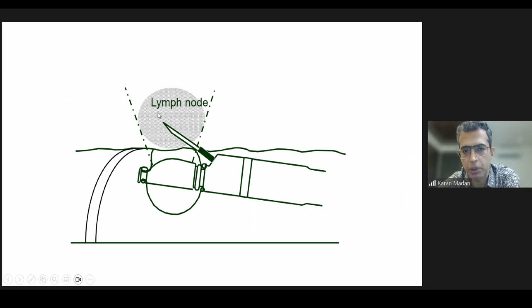Now coming to how it actually looks. This is the real image of two EBUS systems which we have at our facility. These are essentially two parts of the EBUS system. You've got an ultrasound processor, which you see at the bottom, and you've got a video processor. Once you talk about a regular bronchoscope, it just works on a video processor and light source. On the other hand, with the EBUS, you've got this ultrasound processor. These are interlinked together and they are connected to your EBUS bronchoscope.